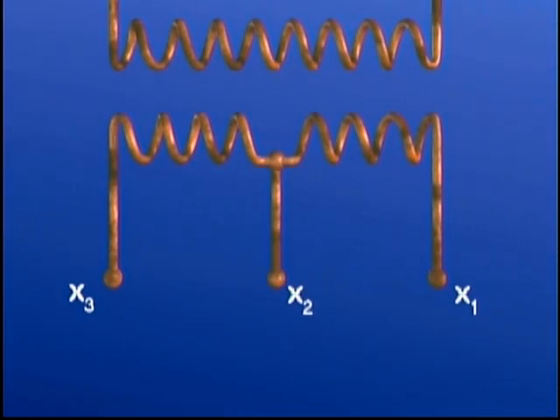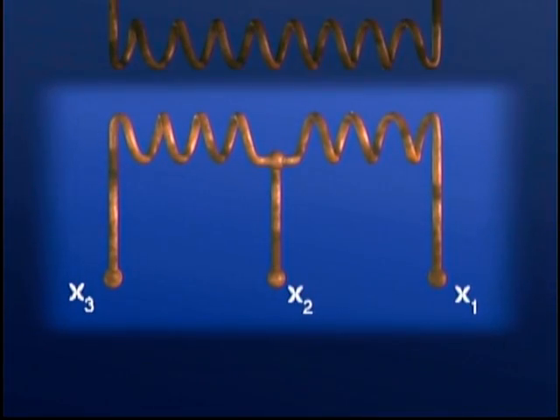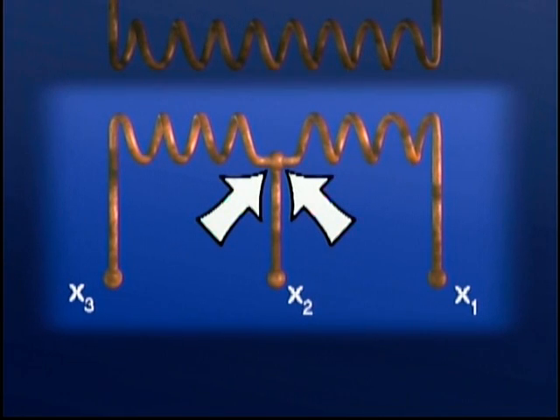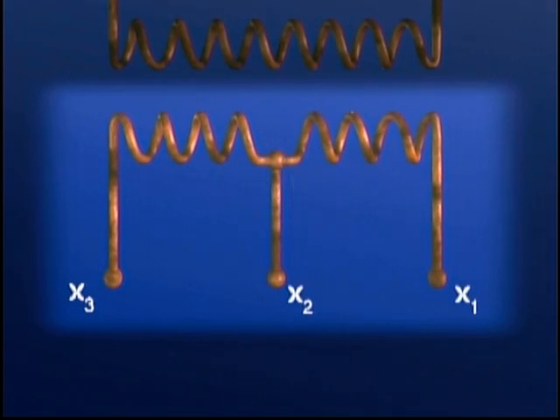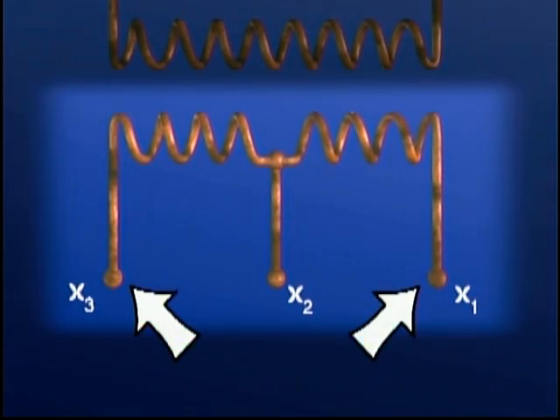Earlier, we indicated that when a transformer is wired conventionally, the ends of the two separate coils that make up the secondary winding are joined together in series at the X2 bushing. The other ends of the coils are connected at the X1 and the X3 bushing, respectively.